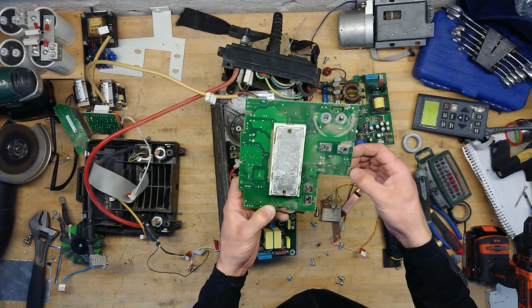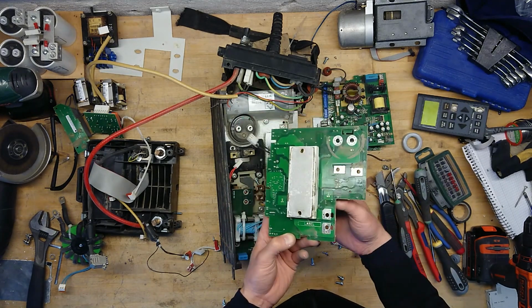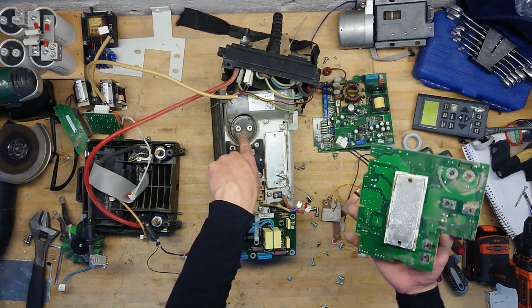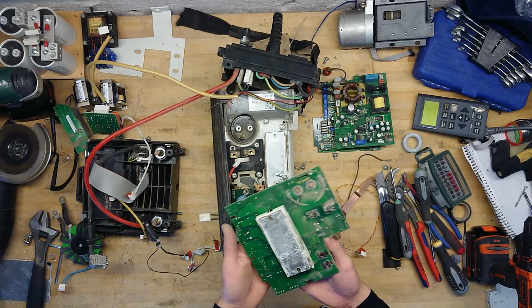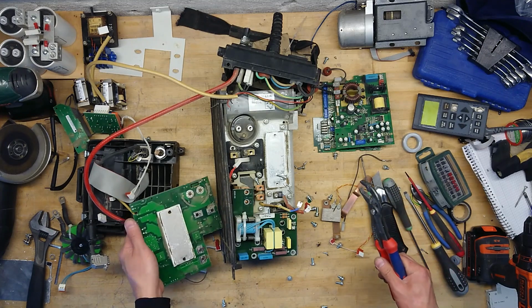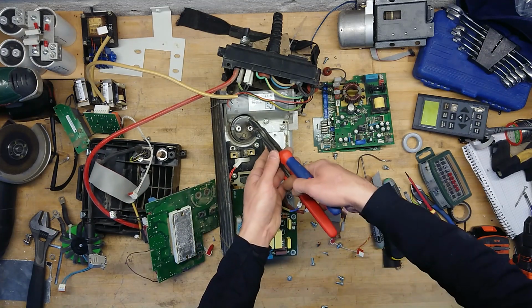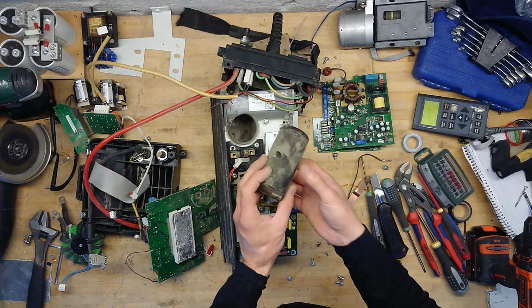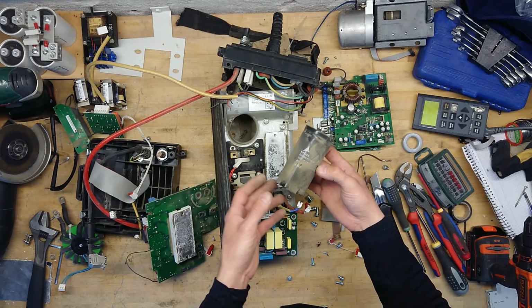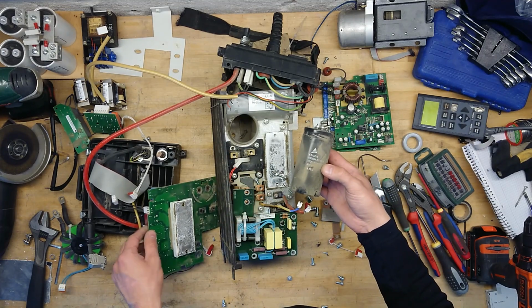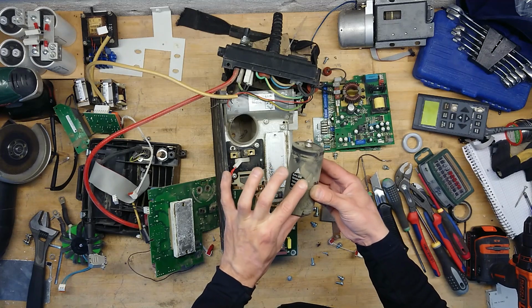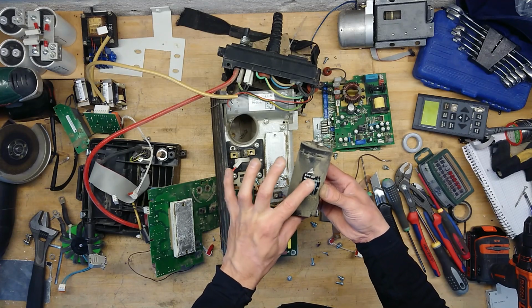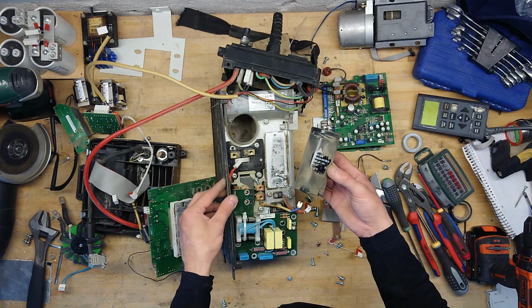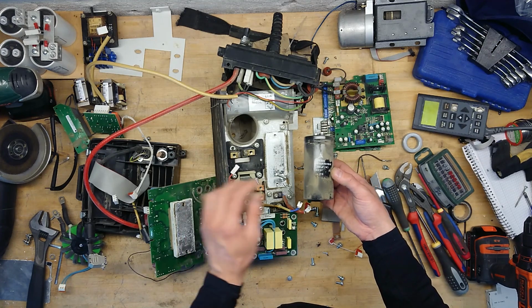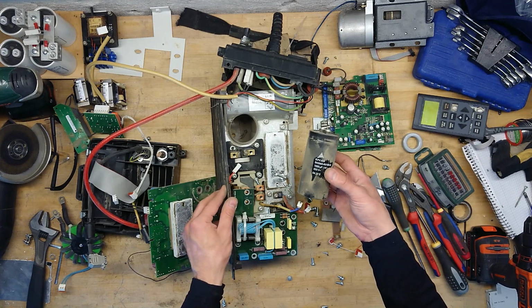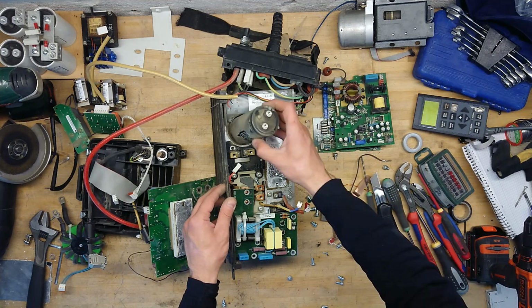Okay, that works fine. Over here we can see where the DC bus filtering capacitor connected to. That just comes up, yeah. Okay, that's dirty as hell. That's sitting right at the fan as well, because this is probably a bit underrated current-wise, and you just cool it a lot instead. But 1000 microfarads at 450 volt AC or DC.